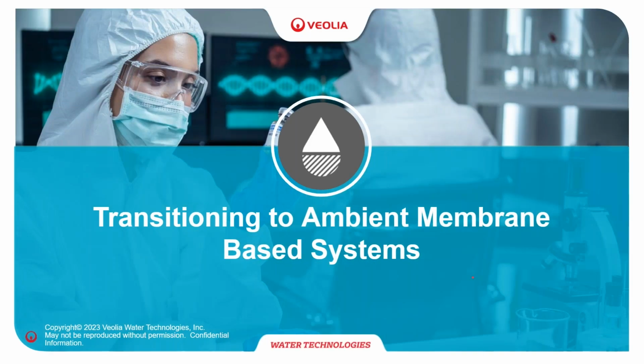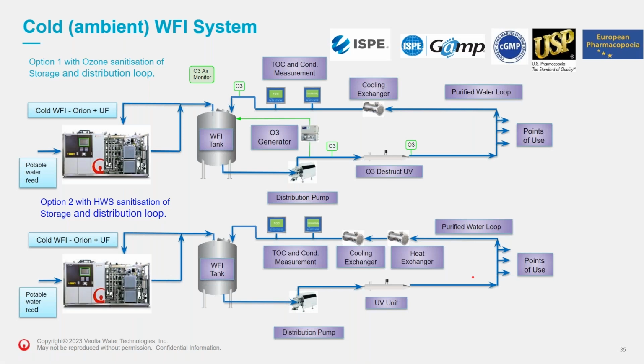So transitioning to this type of system, we talked about cold WFI using RO EDI, making it into a WFI tank. One of the things that has to be considered is the storage and distribution system. If it's a greenfield site, you can have two choices. You can have ozonation as your main sanitization method for the distribution loop, as we talked about earlier, or you can go for hot WFI in terms of your sanitization method for the distribution side.